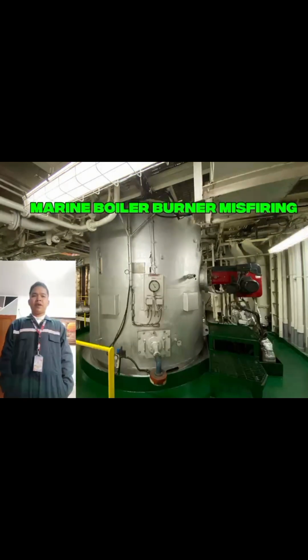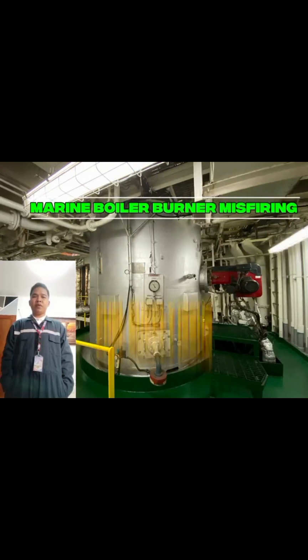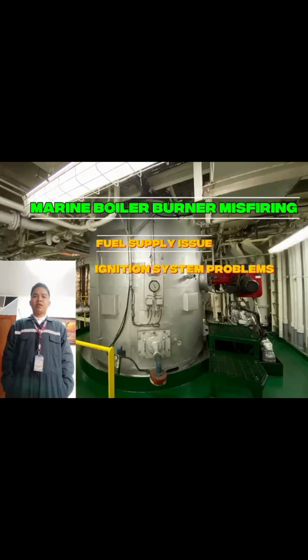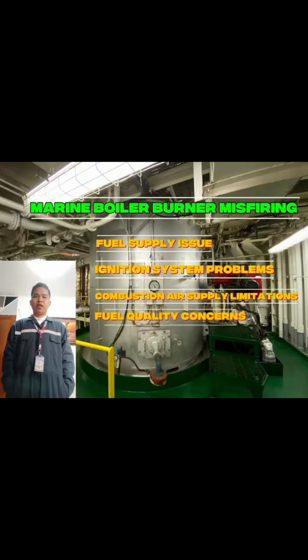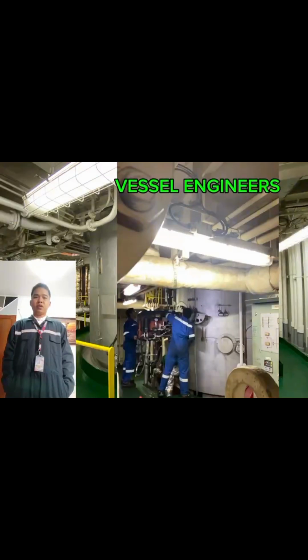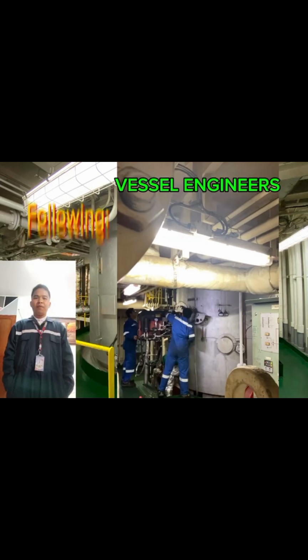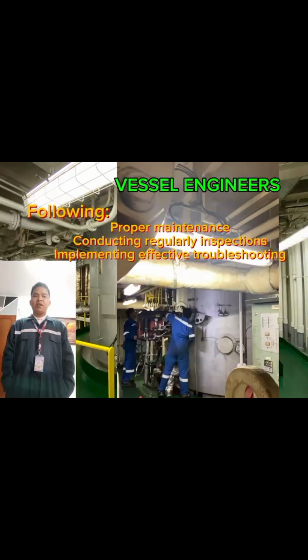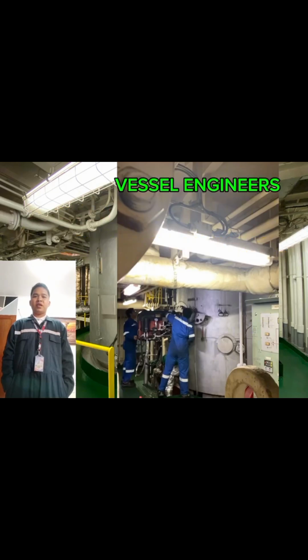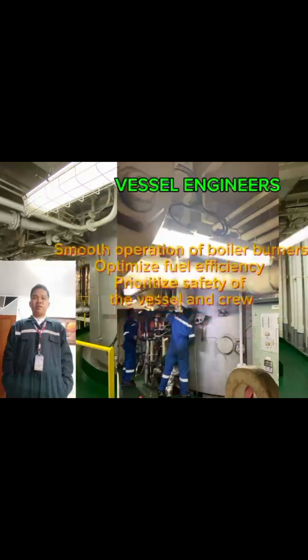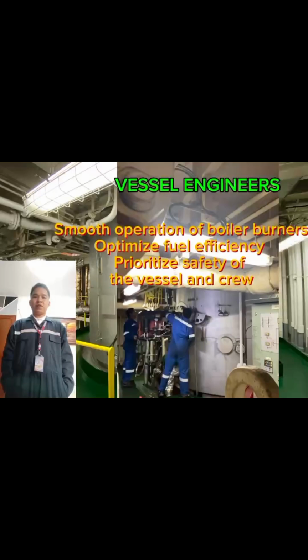Marine boiler burner misfiring can be caused by issues with fuel supply, ignition system, combustion air, or fuel quality. To prevent risk, vessel engineers should promptly troubleshoot misfiring incidents and take safety precautions. By following proper maintenance, conducting regular inspections, and implementing effective troubleshooting, engineers can ensure the smooth operation of boiler burners, optimize fuel efficiency, and prioritize the safety of the vessel and crew.